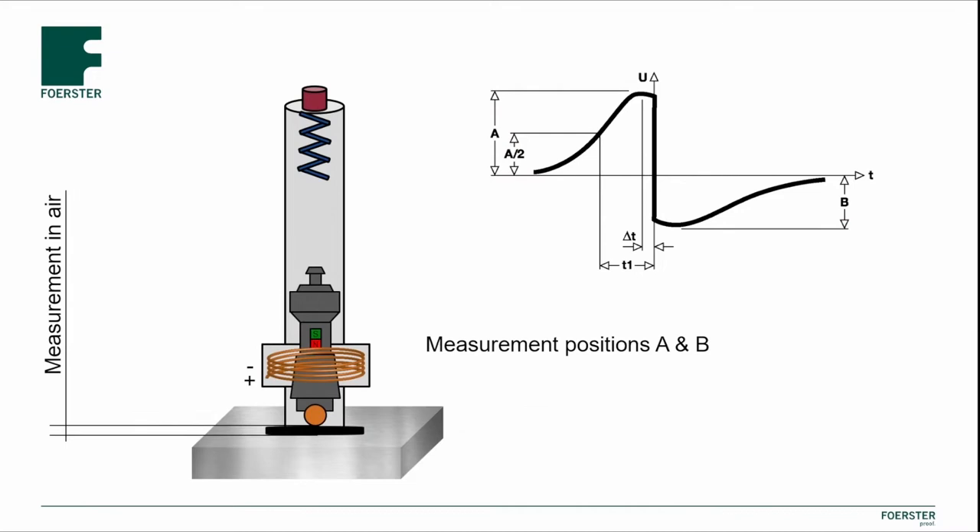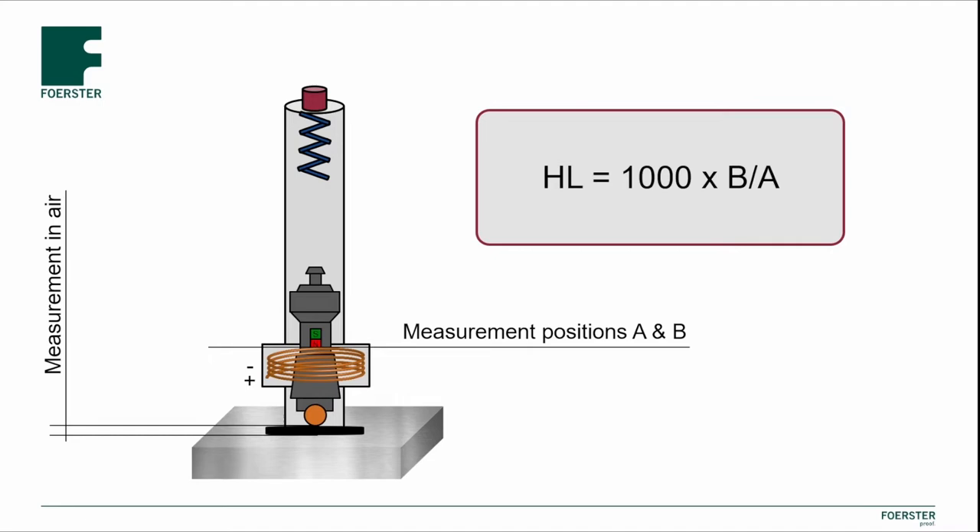The measurement itself therefore takes place shortly before and shortly after the drop of the impactor — in other words, without reference to the actual test piece. The hardness value on the Leeb scale is then calculated from these two values.